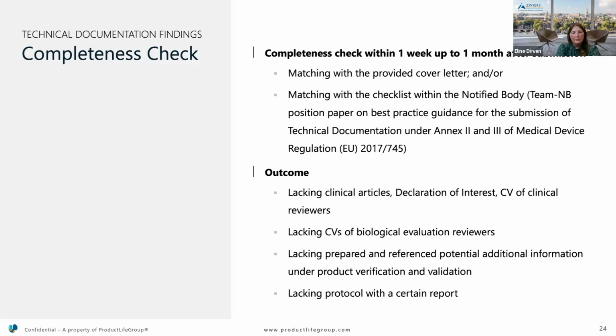We see that especially related to the additional information on the product verification and validation, which are, for instance, the additional requirement for using animal tissue, or if you have a medicinal substance, or in case you have a substance-based device and you need to address the absorptive capacity. But also in cases where there is a measuring function, or that it is provided in sterile condition, or you have a reusable surgical instrument. For those, there are additional requirements, and those need to be addressed.